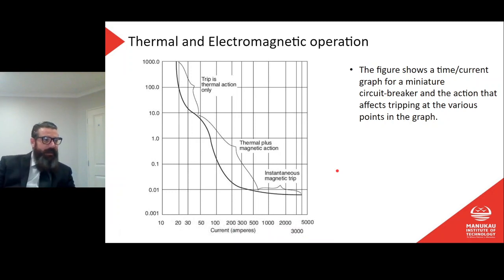There we go. And it has our current at the bottom, 10, 20, 30, 50, 100, etc. So around here we've got about 20 amps. This is our 20 amp line here. So somewhere around the 20 amp mark, it's going to trip, over 100 seconds. This is the number of seconds that it's going to trip in. So over 100 seconds. Once we hit the 20 amps, it's going to start coming down pretty quick. So we're going between 100 seconds for 20 amps down to a bit over 10 seconds for 30 amps. That's our thermal action only.